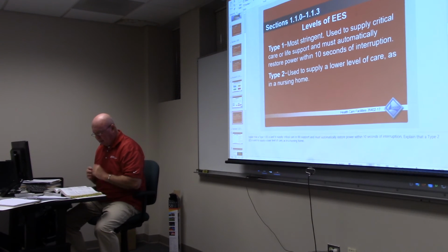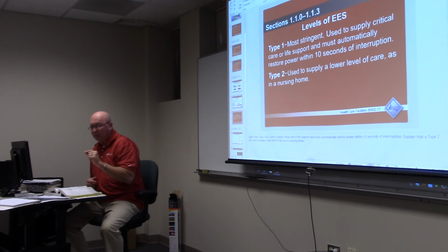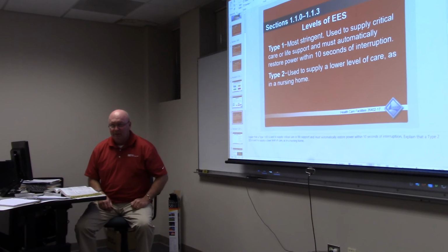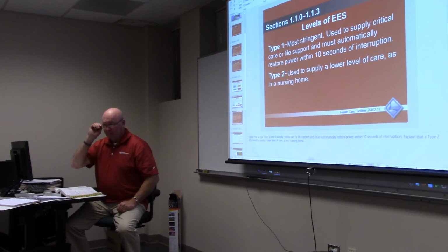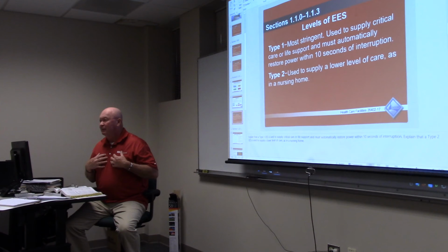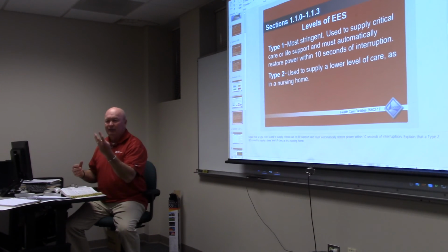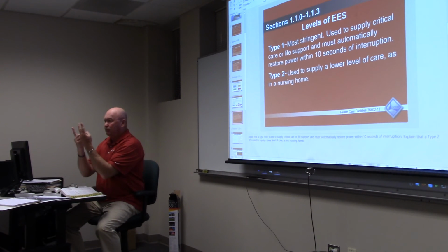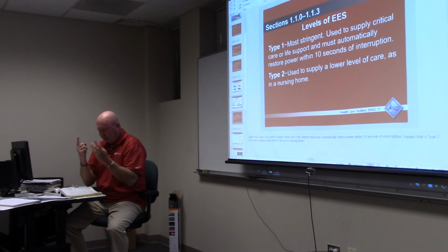Okay, and if you read here, there's even a bit different. Look at the next paragraph. Branch circuits serving patient bed locations shall not be a part of a multi-wire branch circuit. In other words, it needs to have its own neutral. Because a multi-wire branch circuit means you can put 3 wires on one neutral, right? But I think in reading that, for each branch circuit, we want its own neutral.